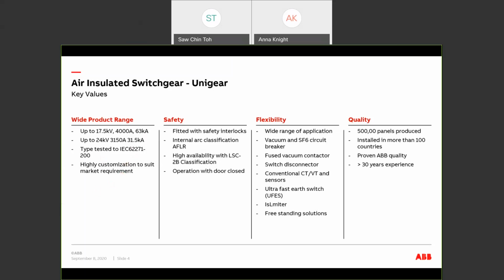Next item to be considered is the safety and reliability of the panels. UniGear ZS1 has been fitted with safety interlocks to prevent maloperations. All operations are carried out with door closed. Operator can only open the HV compartments when the circuit breaker is isolated and panel is earthed properly. The switchgear has also been type tested to internal arc according to IEC standards. Operators are protected from all sides of the cubicle in an event of arc fault.